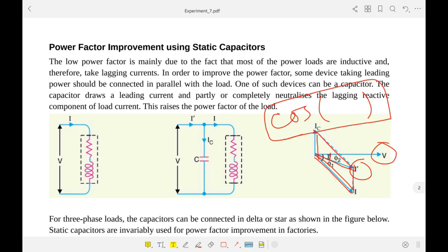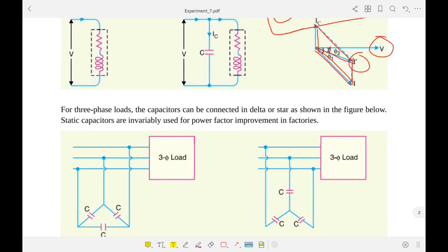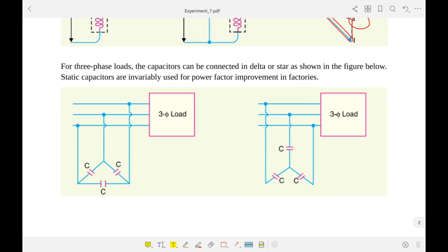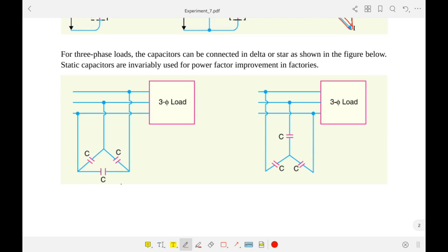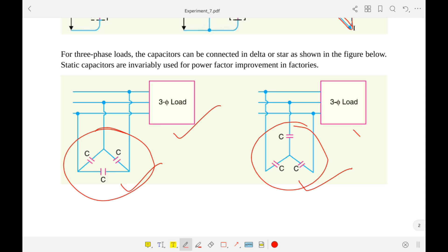The minimum angle is zero degrees in the case of a purely resistive circuit, where power factor is unity. That's why we use capacitors in parallel for power factor improvement using static capacitors. In three-phase networks, this can be either delta connection or Y connection, and the capacitors must be connected in parallel with the three-phase loads.